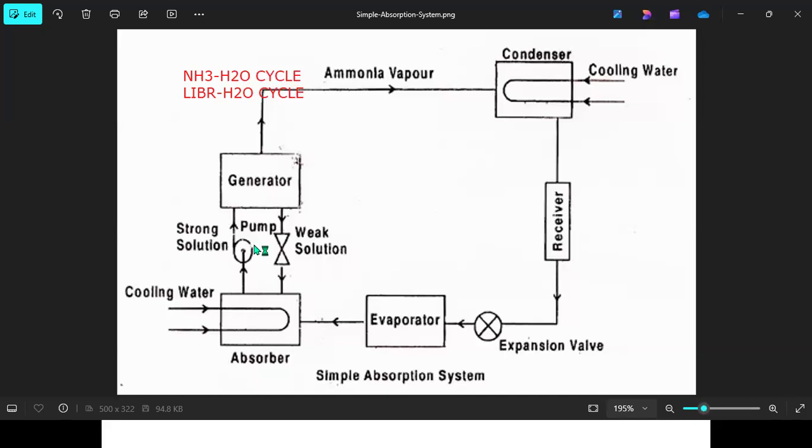That's it. So here, a small problem will arise. When we mix this ammonia with normal water, which means room temperature water, what will happen? Through this mixing, a lot of heat is dissipated during the process itself. Am I clear? That means when ammonia is mixed with the water, it creates more heat dissipation across the absorber chamber, which results in a higher temperature of water.